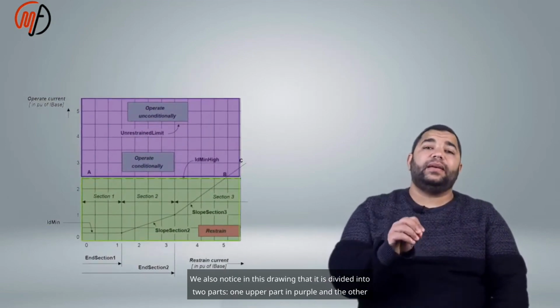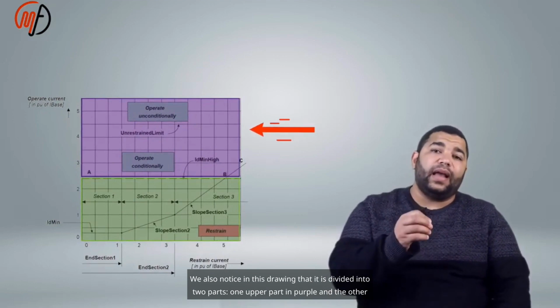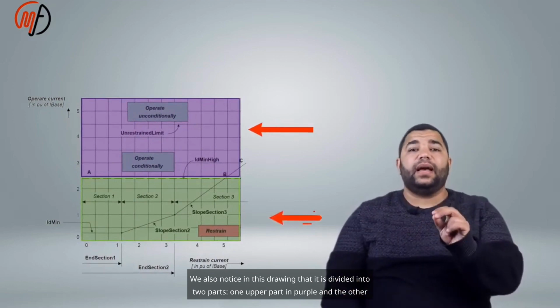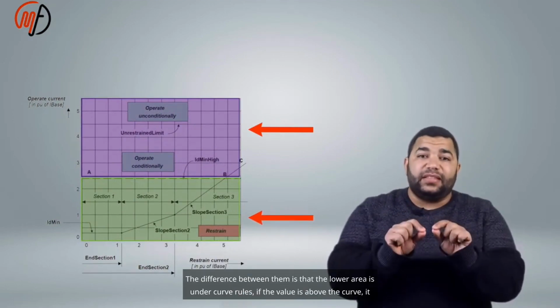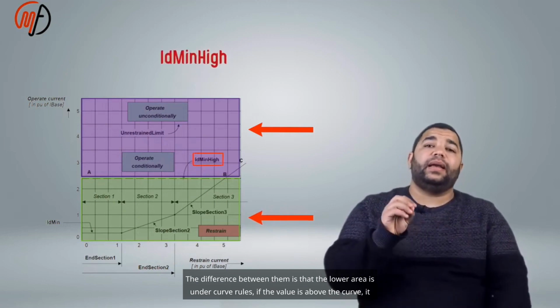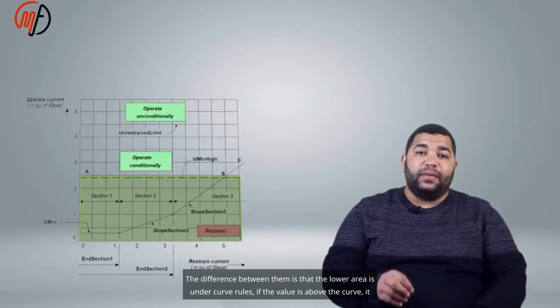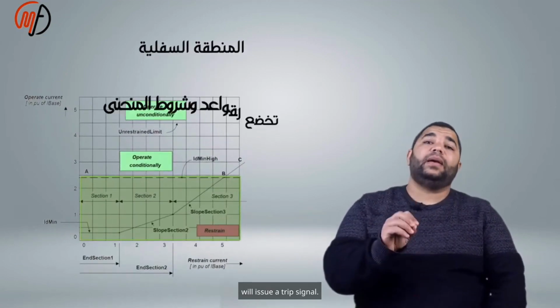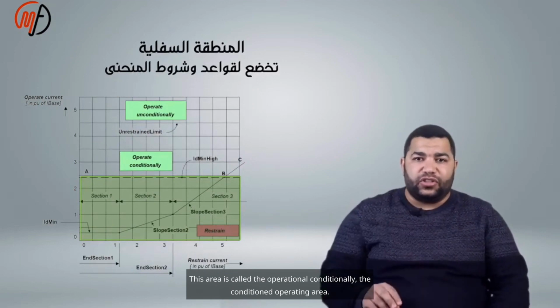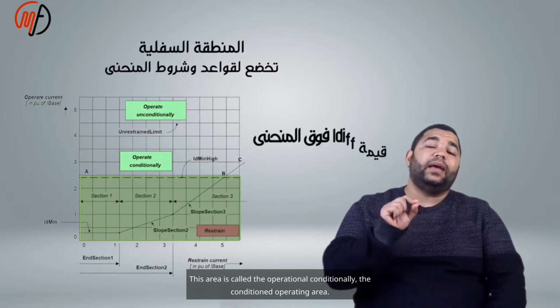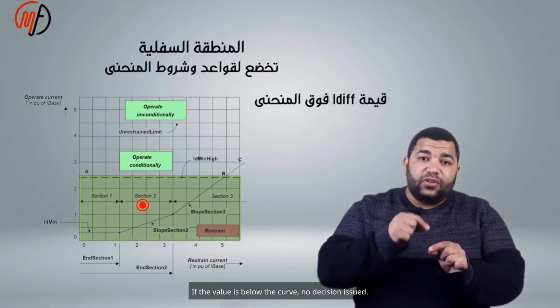We also notice in this drawing that it is divided into 2 parts, one upper part in purple and the other lower part in green. The difference between them is that the lower area is under curve rules. If the value is above the curve, it will issue a trip signal. This area is called the operational conditioned operating area. If the value is below the curve, no decision is issued.